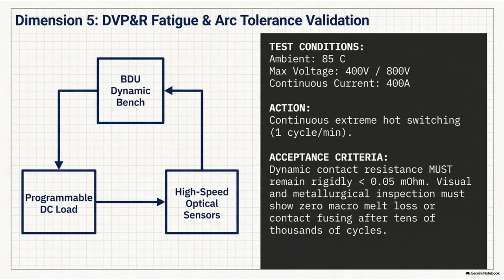Let's look at the first major validation test, the hot switching fatigue test. We spent the first part of this deep dive talking about how chemically and electrically terrible hot switching is. This is where they intentionally do it on purpose, right? They do it thousands of times. Validation engineers utilize a massive, highly specialized piece of laboratory equipment called a BDU dynamic test rig, the battery disconnect unit rig. They take the freshly manufactured contactor and they place it inside a heavy-duty environmental test chamber.